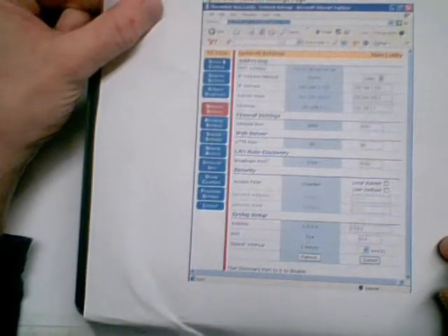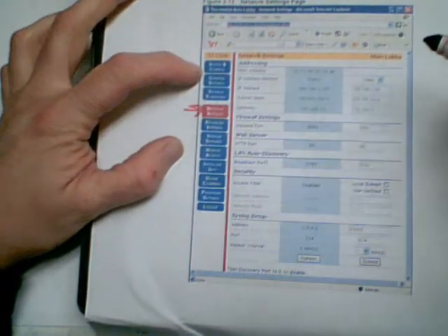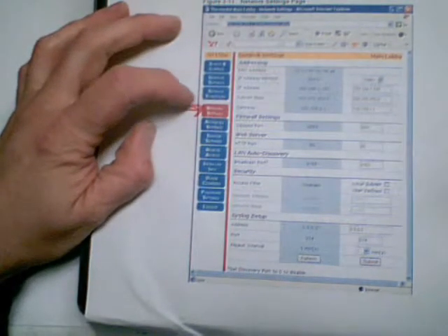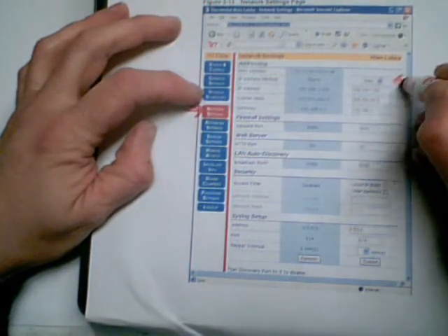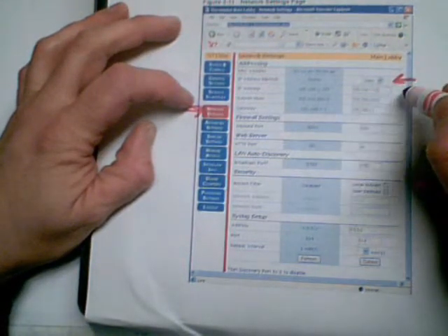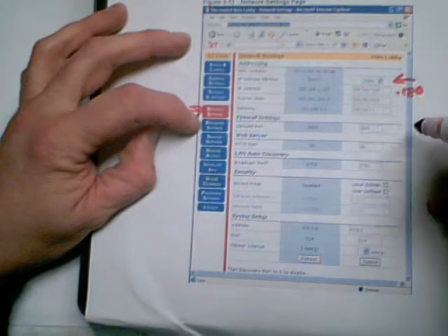Okay, so let's take a look at some printouts of what the thermostat looks like and where these settings are made. We haven't exactly got a world-class video going here, so I'm not sure how well you can see this, but there is a tab on here called Network Settings. This is only available to the admin login, and this is how the thermostat communicates to the network. It has its own MAC address, but we have them configured for static IP, and this is just out of the user manual, so this is not accurate. Ours is .180 for the sanctuary. Subnet mask, the gateway, as a matter of fact, is correct for us, but that's our gateway to get out to the internet and to the wide area network.